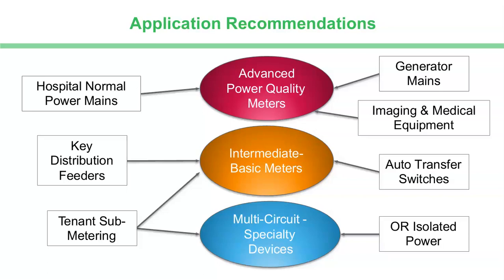When we start looking downstream at key distribution feeders and things like transfer switch loads, that's where the intermediate meters are typically applied. So you've got high-end power quality meters feeding more of the intermediate meters down in the distribution and at the transfer switches. Down on the multi-circuit specialty, you see on the right-hand side, I mentioned operating room isolated power. That's another unique thing to healthcare, where we have the requirement in wet areas delivering patient care that it either needs to have ground fault or isolated power. Where you have isolated power, we do have the ability with power monitoring systems to also be able to monitor that, know the total hazard current, and if a dangerous or hazardous situation is there, all of the data is logged, stored, alarmed, and you notify the appropriate people.